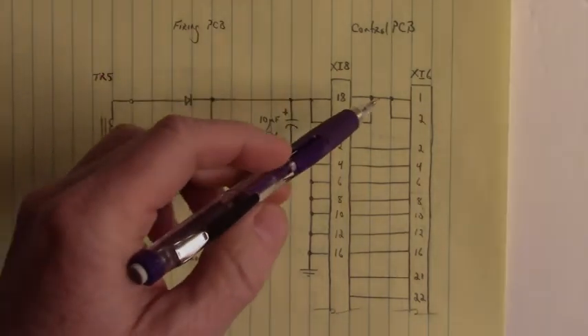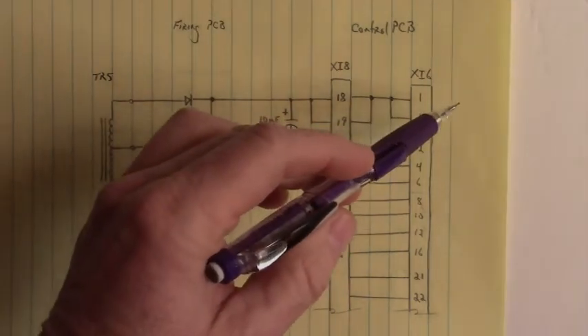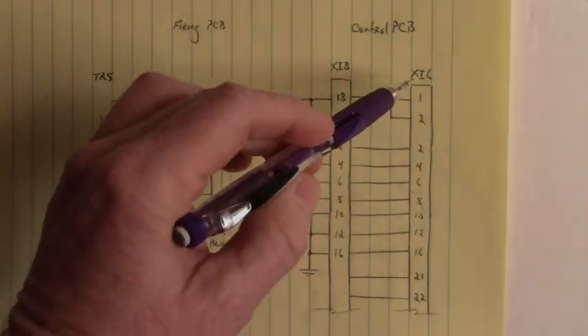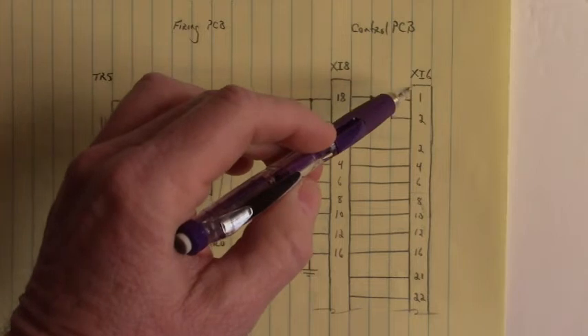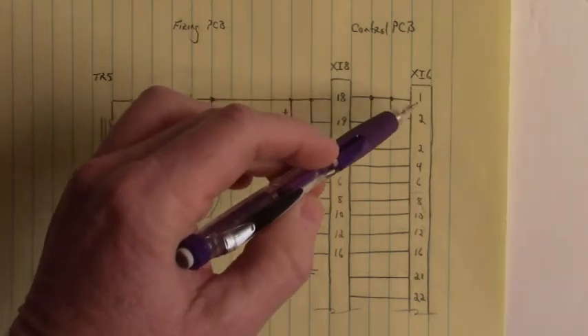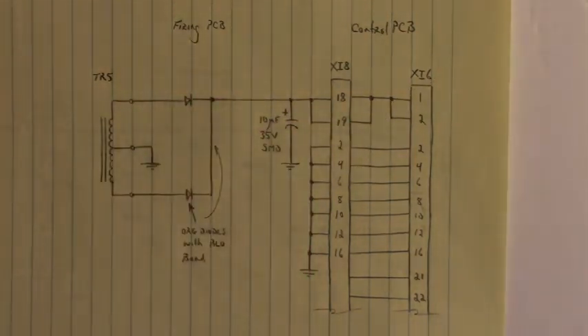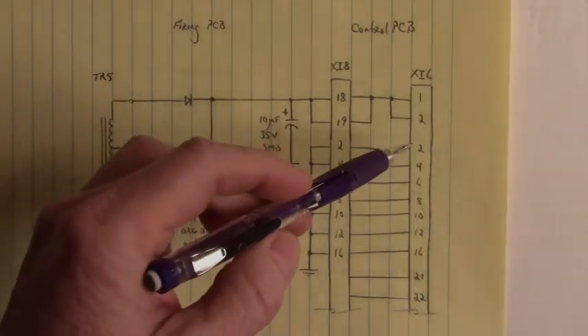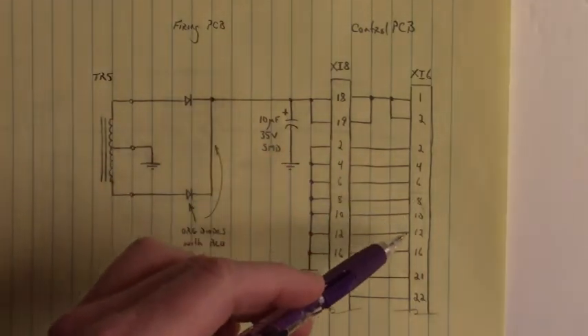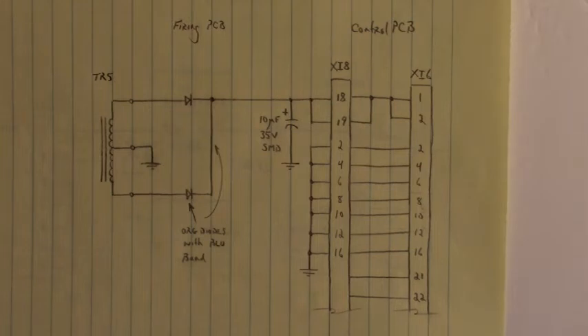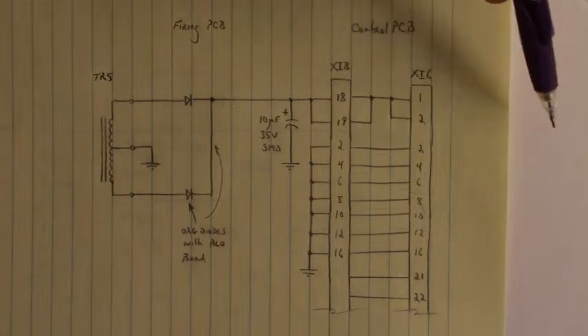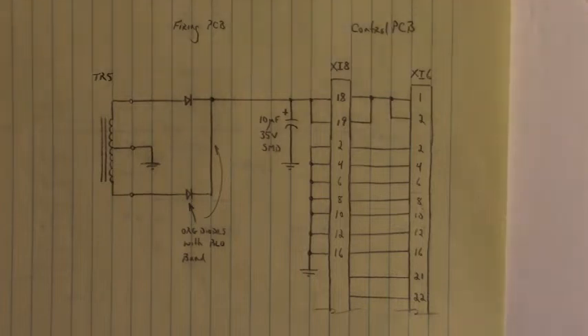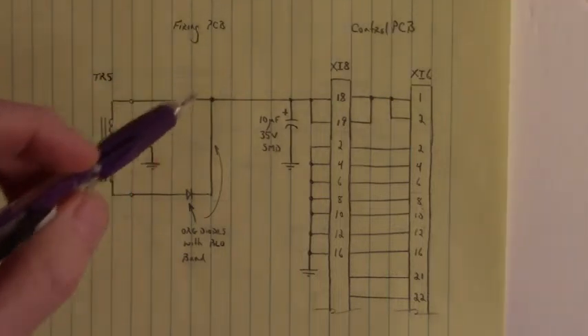18 and 19 through the control board run back out another ribbon connector, XIC, on pins 1 and 2. And its grounds being on 2, 4, 6, 8, 10, 12, and 16. So we route this voltage into the control board and back out the control board back to the power board, the firing PC board.